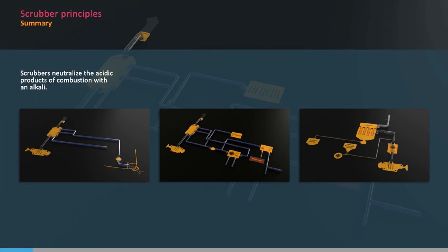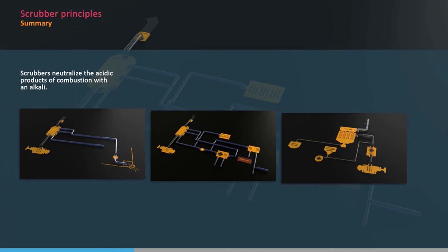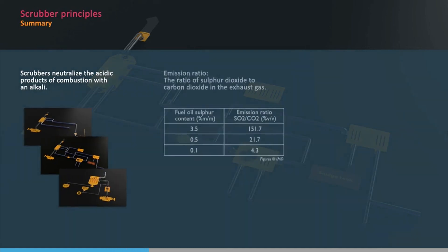Scrubbers work by neutralizing the acidic products of combustion by bringing the exhaust gas into contact with an alkali. The IMO use the emission ratio, which is the ratio of sulphur dioxide to carbon dioxide in the exhaust gas, by volume, as a measure of the amount of sulphur products in the exhaust gas.